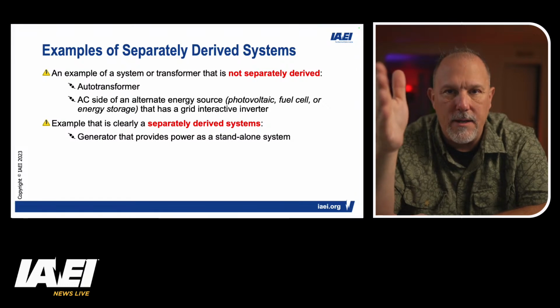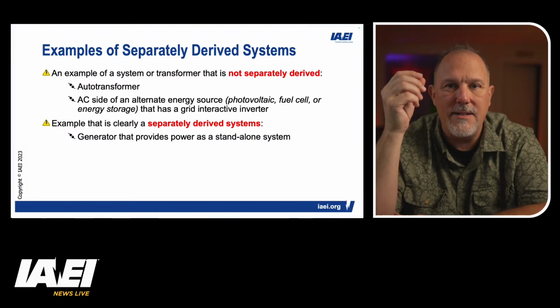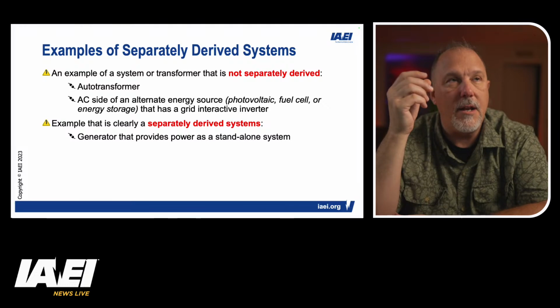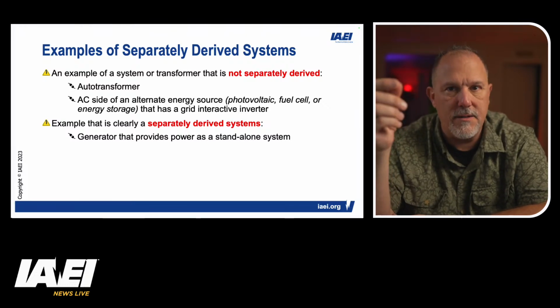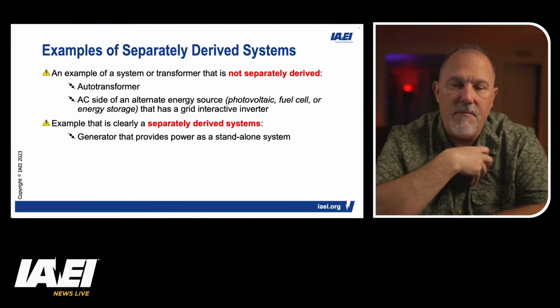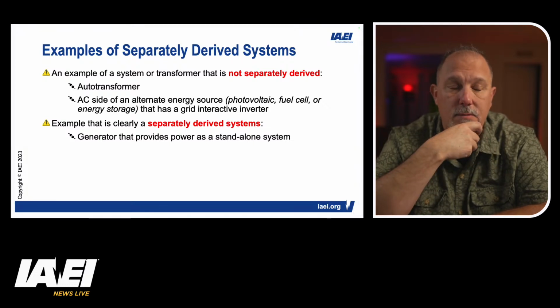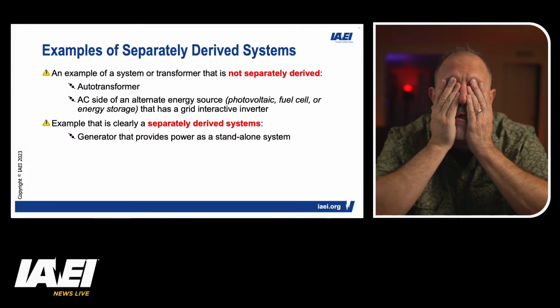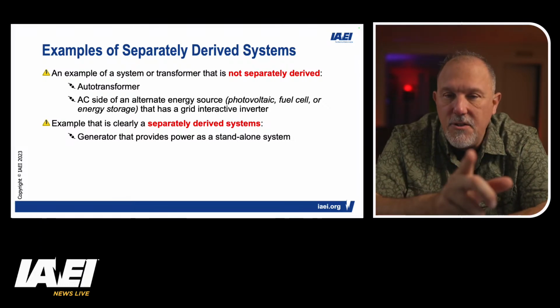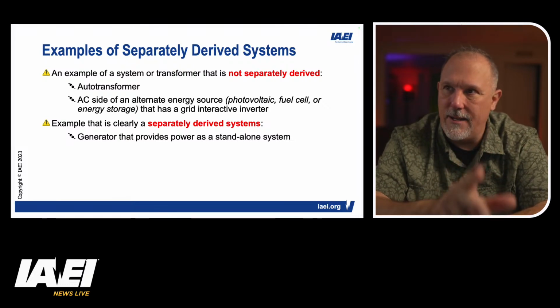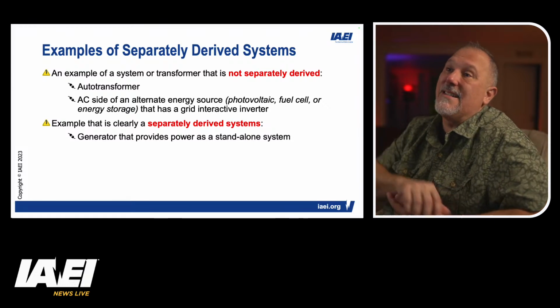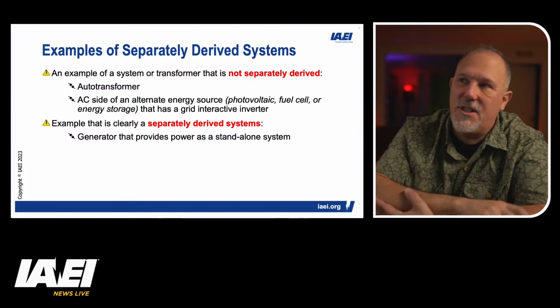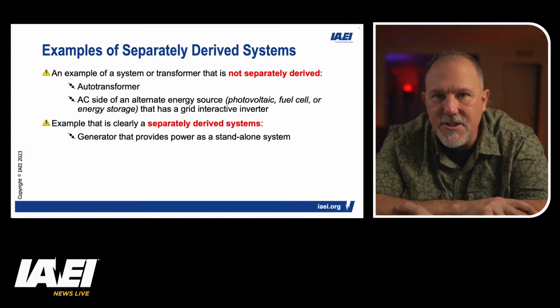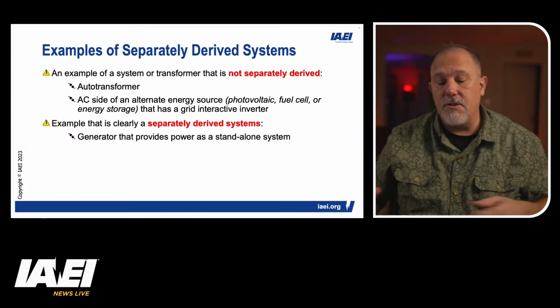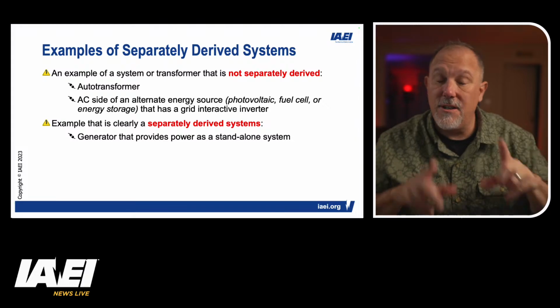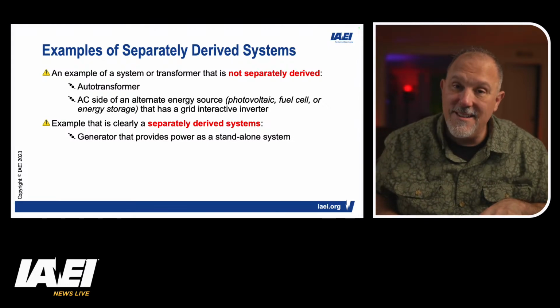Hopefully, at some point in all of these programs, Article 100 is going to gain your respect. Because I know for me, Article 100 was like, I just want to go to sleep, until you realize how important it is. An example that is clearly a separately derived system is a generator, a standalone generator. Now, if that generator is interconnected and you have a transfer switch, if you're switching the neutral, right?